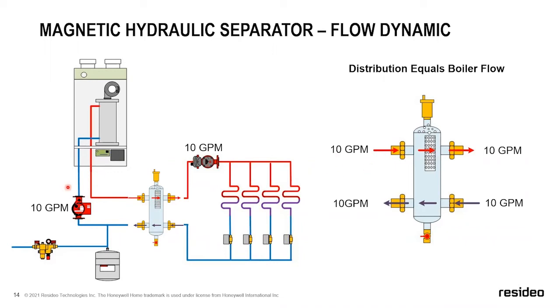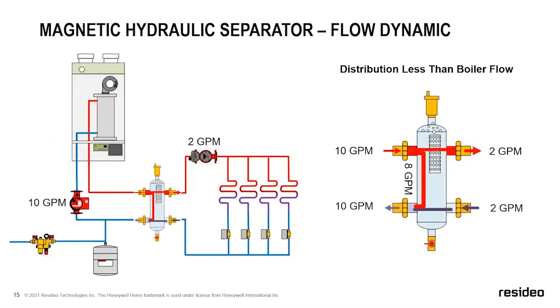But in this example, if you've got a pump here driving 10 gallons a minute, it's creating a pressure differential, which is driving flow through this device. At the same time, you've got 10 gallons a minute. It's basically created a full flow situation. So you have 10 gallons a minute coming in, 10 gallons a minute going out to the system, coming back and coming back to the boiler. This rarely ever takes place in modern systems, but this can happen. This is a much more realistic example of what's going to take place.